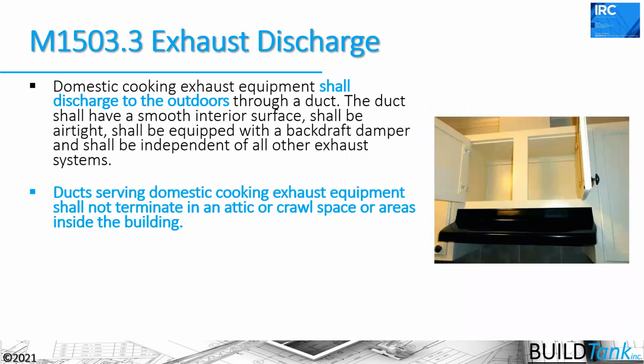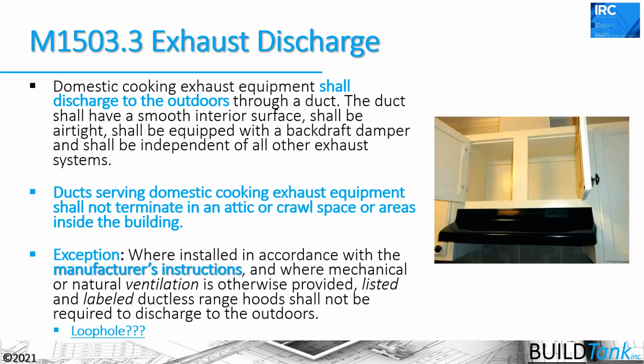This means that we need to discharge to the outdoors, and what I really am pointing out with this slide is that there's a loophole for these recirculating hoods. Unfortunately, manufacturer instructions still have a lot of sway with regards to installation when we're talking about the codes here, and these manufacturer instructions, and this exception in the code, give us a loophole to continue to use recirculating hoods. But from a ventilation perspective, from a long-term durability and a health and safety perspective, we should really get rid of recirculating hoods as well here.